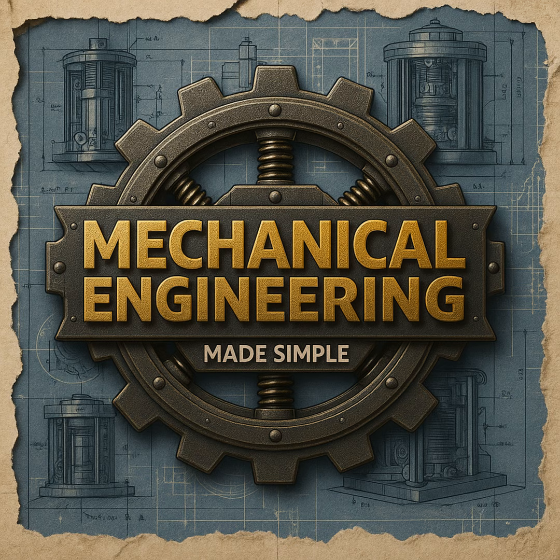Which is, I mean, totally fine if I just want to know if the machine is shaking itself apart. If the overall vibration is high, I know I have a problem. Sure, it's a good overall health indicator. But if I want to isolate the specific part that is failing, if I want to find the one broken instrument in our chaotic orchestra, that time domain is practically useless. Everyone is talking over each other. It is extremely difficult to diagnose from a raw time wave.